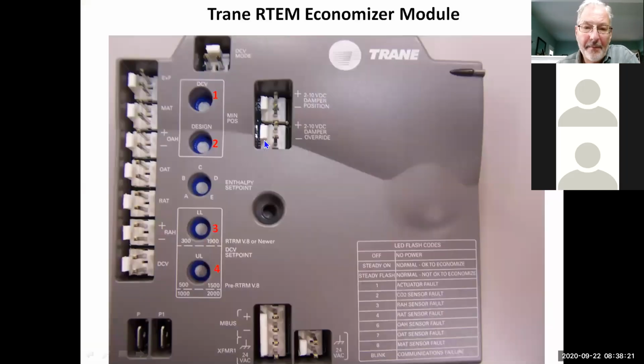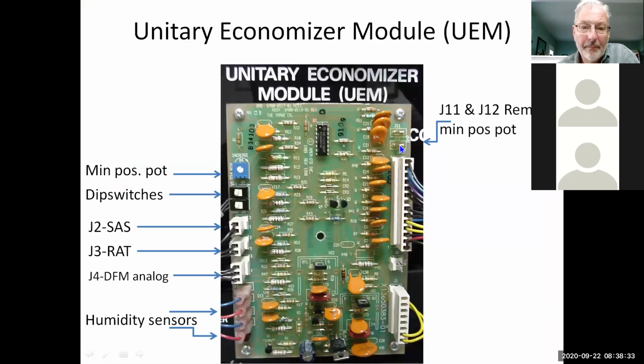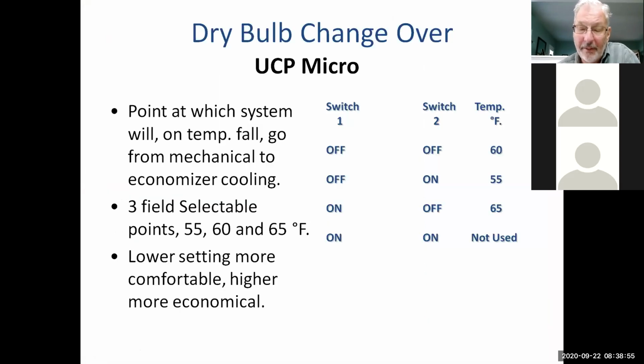If you look at the Reliatel one, it's almost identical again, but you don't have that Y1 in and Y2 in input. Otherwise, they're pretty much identical setup. I'm not going to spend a lot of time on these because they're kind of fading away. We haven't used this control since 2000, so it's already 20 years since we've been using it. There's a ton of them out there yet. The only thing I can tell you about these is if there's water damage on them and you're having problems, replace them because they need to be replaced.